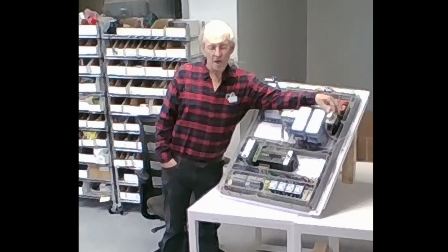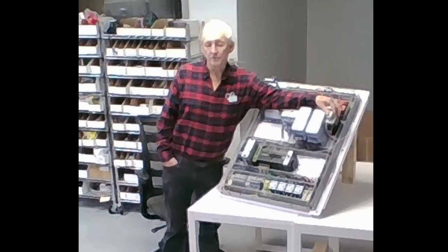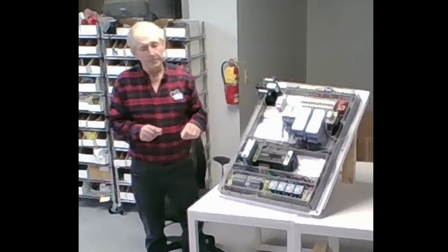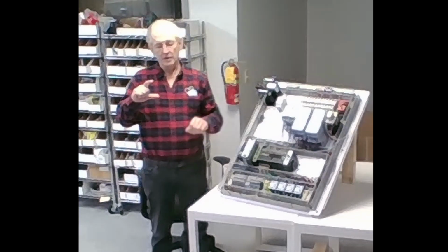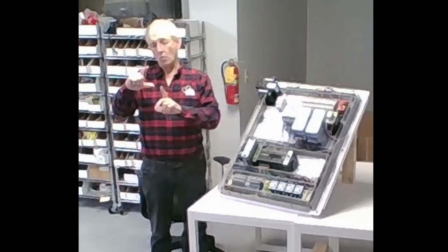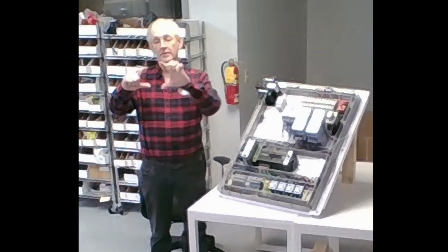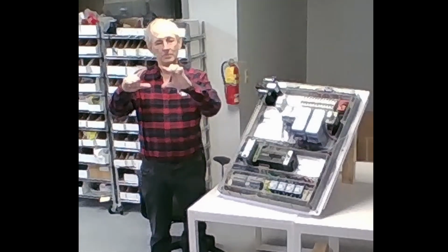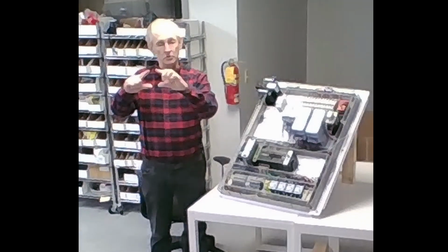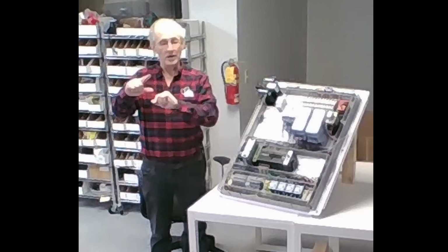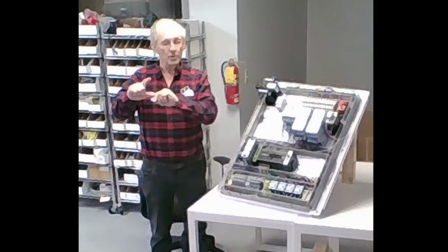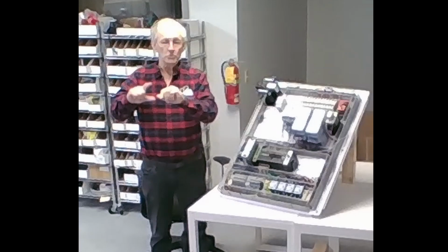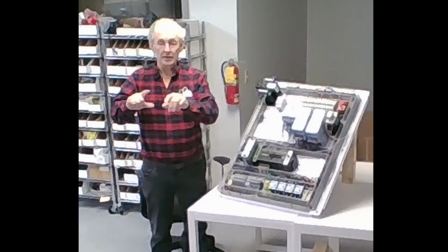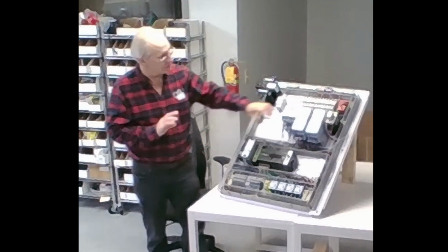They call this a contactor and not a relay. And there's a difference. In a contactor, there's a wire hooks here, and there's a jumper that moves in and out that's conductive that goes between them, so it breaks the load twice. And the reason for that double break is that it reduces arcing because it opens faster. You get a bigger gap quicker. And so that's a contactor.